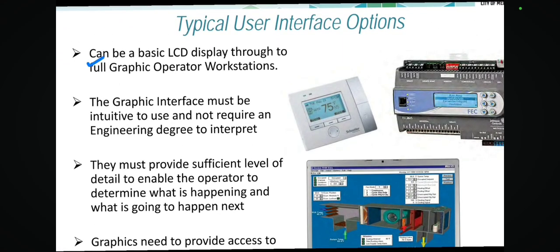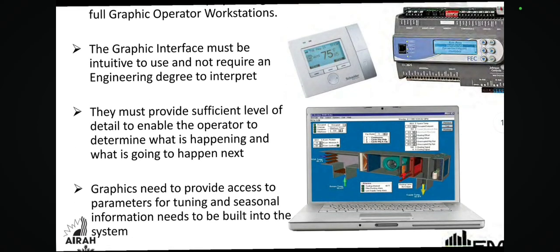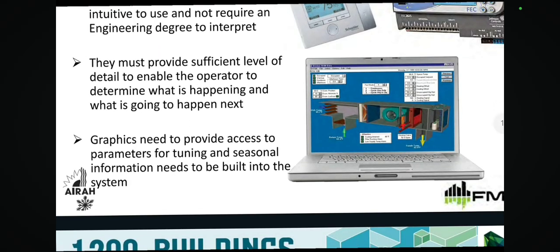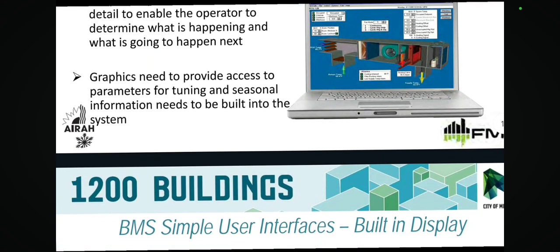This can be a basic LCD display through to a full graphic operator workstation. The graphic interface must be intuitive to use and not require an engineering degree to interpret. It must provide a sufficient level of detail to enable the operator to determine what is happening and what is going to happen next. The graphics also need to provide access to parameters for tuning, and seasonal information needs to be built into the system.